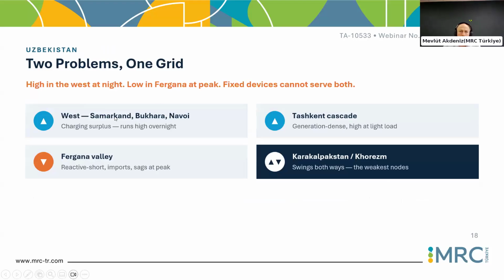Next one, please. Yeah, we have similar or different problems in the same grid regarding the Uzbekistan grid, with a wide range of long lines. From east to west, we have some long lines. They are less loaded during the night or low load case, and with long lines, surplus reactive power occurs. So we need some dynamic reactive compensation, even from synchronous generators maybe, or SVCs and STATCOMs, but maybe shunt reactors alone are not enough for this solution at this point.